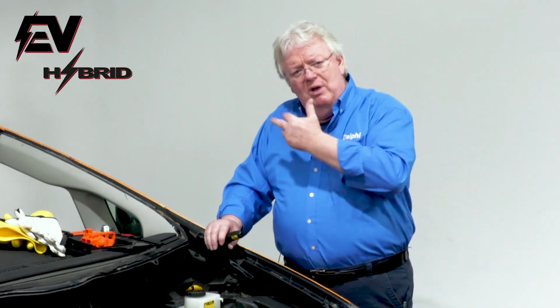So you still don't want to ever touch any high voltage connection without proper personal protective equipment - class 0, 1000 volt gloves, tested and inspected every time you use them, and tested every 6 months by professional service. So when we see 2 milliamps, it doesn't sound like a lot, but it is enough - you could probably feel it at the very least, and if there's a problem, it could be worse.